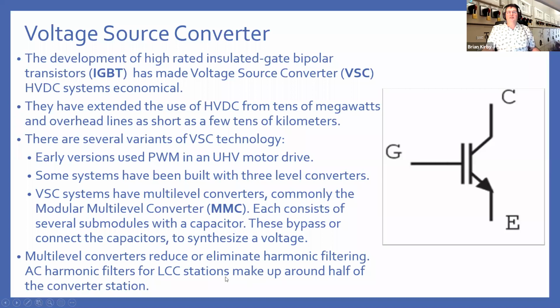Another advantage VSCs have is that the way LCC systems work, they generate lots of harmonics. So you have to have filters to reduce the harmonics on your AC network. So on an LCC station, you will see a large filter bank around the converter station in order to maintain the noise profile required for the AC network. Whereas with VSCs, it's much less of an issue because you have a much finer resolution in your voltage waveform generation.